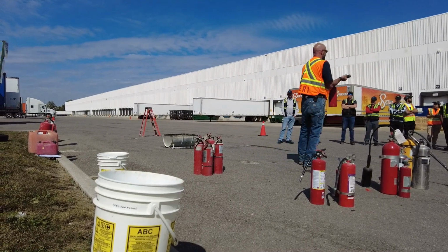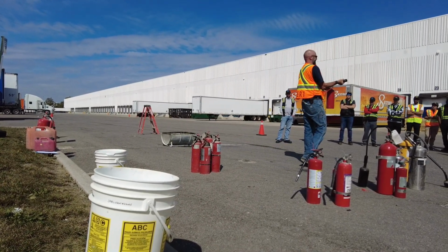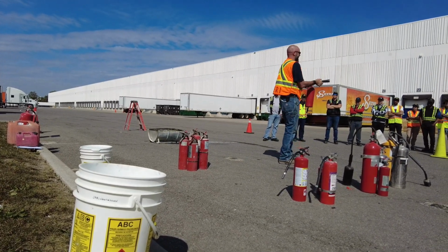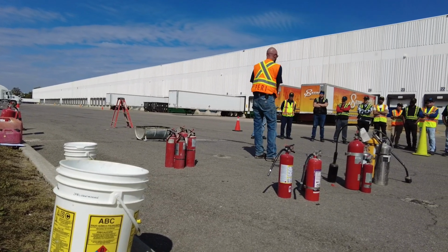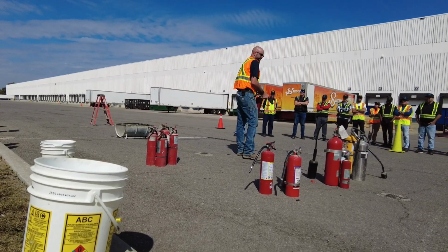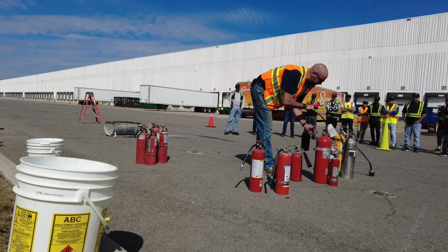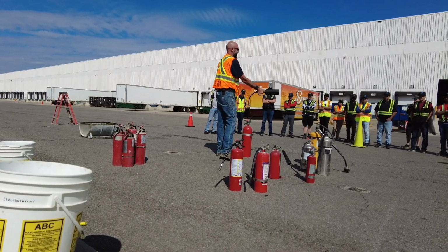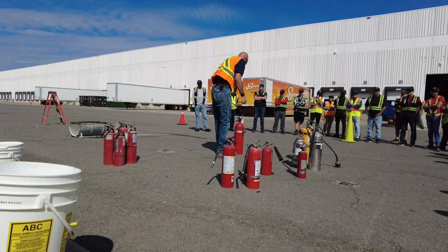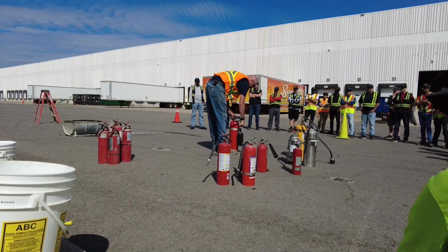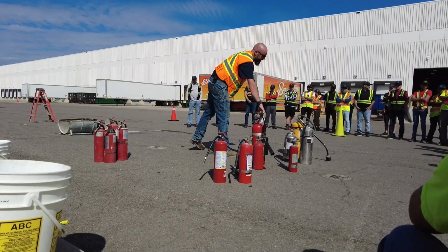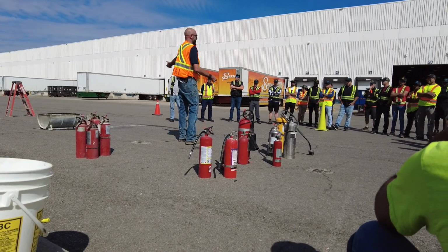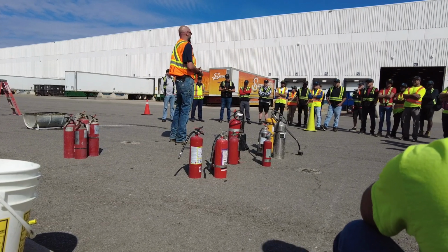With this, you've got to be careful that you don't grab it out here. These come out at minus 45. You will get frostbite. So for the little ones, like I did, just shoot it off. You can see the bigger one here. This is a 15-pounder. It's got a handle built in to direct the gas. Again, these typically you're only going to see near electrical rooms or sensitive equipment because you're not going to get the powdery residue into other equipment.